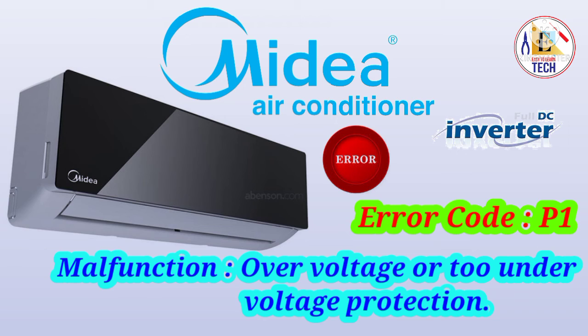Again, if you are getting this same error P1, it means your outdoor PCB is faulty. The outdoor PCB is not converting DC current properly, so there is an over voltage and under voltage in your outdoor PCB. So you have to change the outdoor PCB and you will get the solution for the error P1.